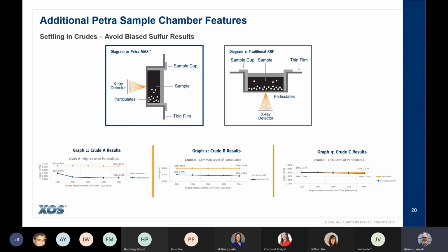In the second example, there's what we call a common level, typical particulate concentration. You see a difference, traditional testing at 0.73, and then the Petra Max giving you 0.85. Again, that's significant. And even in the third example, you'll see very little particulate. There is some difference, I think 1.28 versus 1.31 sulfur. So that vertical chamber is a big win for us. We think it's a great feature for the labs to help them produce more accurate data.